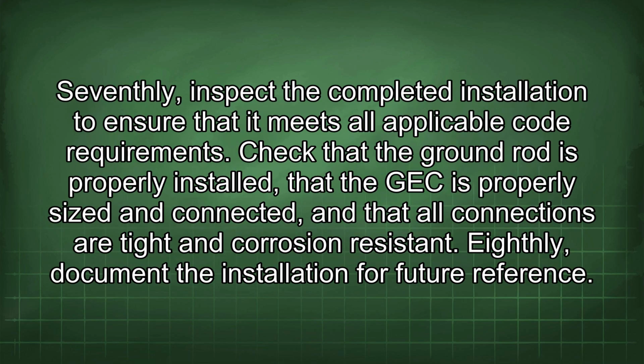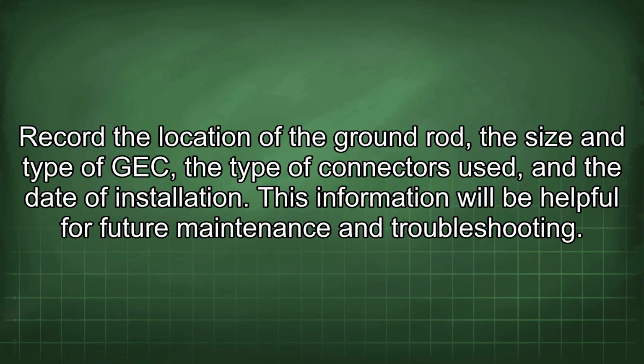Seventhly, inspect the completed installation to ensure that it meets all applicable code requirements. Check that the ground rod is properly installed, that the GEC is properly sized and connected, and that all connections are tight and corrosion resistant. Eighthly, document the installation for future reference. Record the location of the ground rod, the size and type of GEC, the type of connectors used, and the date of installation. This information will be helpful for future maintenance and troubleshooting.